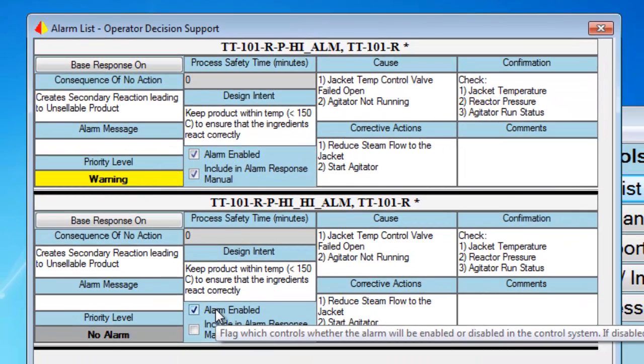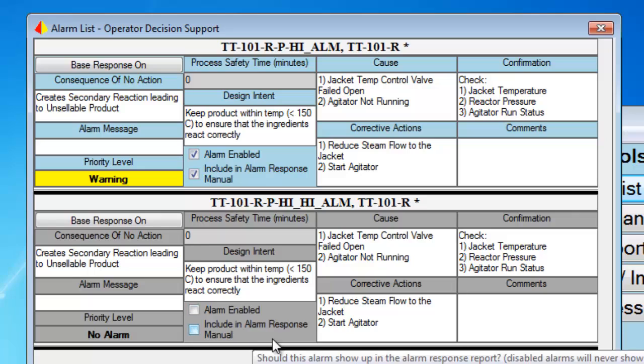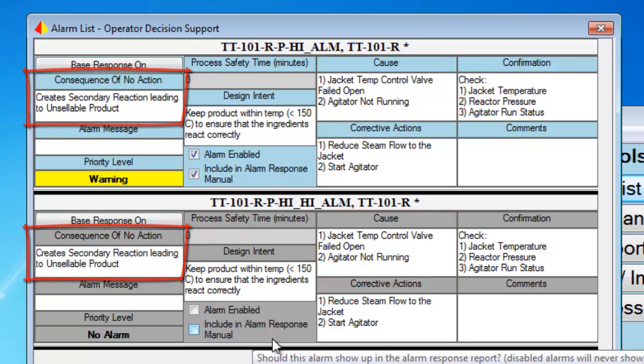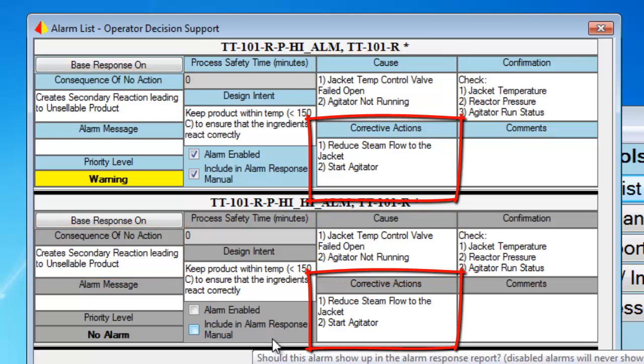Now that we've completed our review of the high alarm, let's turn our attention to the high-high temperature alarm. When we reviewed the cause, consequence, and corrective action for the high-high alarm, we found no differences from the high alarm. Thus, we do not need this alarm and it can be disabled. For the high-high alarm to be valid, either the cause would need to be different, the consequence would need to be different, or the corrective action would need to be different — in kind or degree.